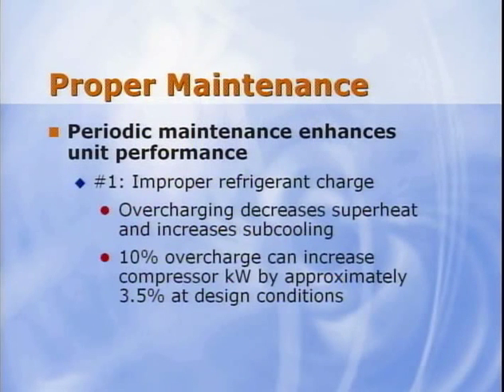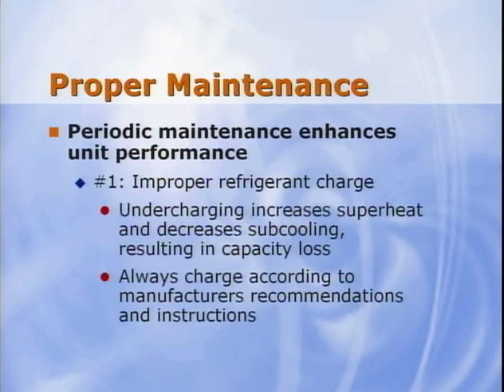practice. And finally, probably the number one energy robber: improper refrigerant charge. Improper charging can decrease energy efficiency and capacity. Overcharging the system decreases superheat and increases subcooling. A system overcharged by 10% can increase compressor kW by approximately 3.5% at design operating conditions. An undercharged system increases superheat and decreases subcooling, resulting in capacity loss. Loss of capacity means that mechanical cooling hours increase to maintain temperature. It is critical to maintain the refrigeration system balance point by charging according to the manufacturer's superheat and subcooling temperature recommendations. And you should always follow the manufacturer's charging process, which is usually outlined in the Equipment Installation Operation Manual.